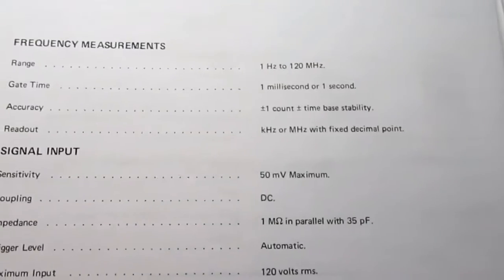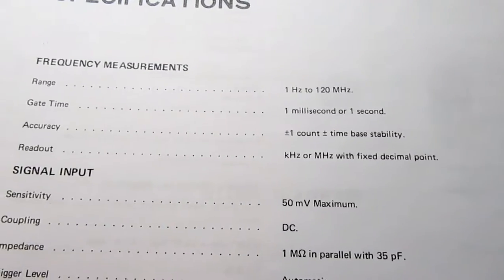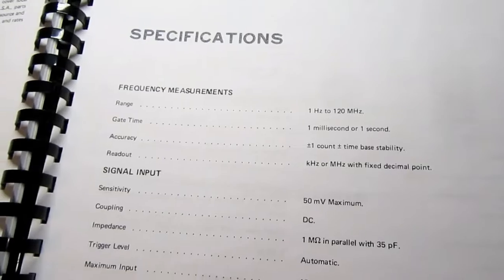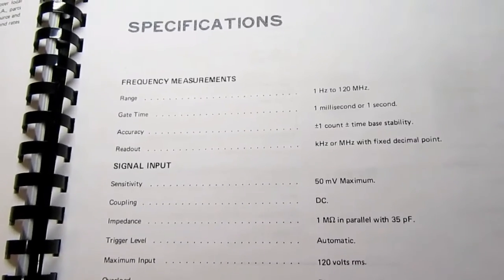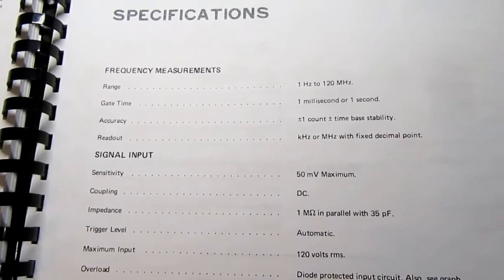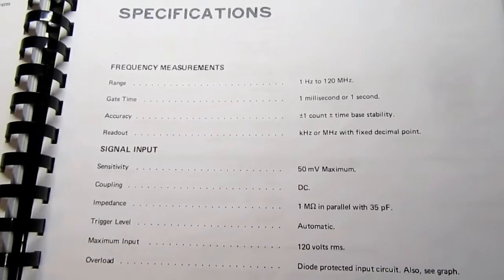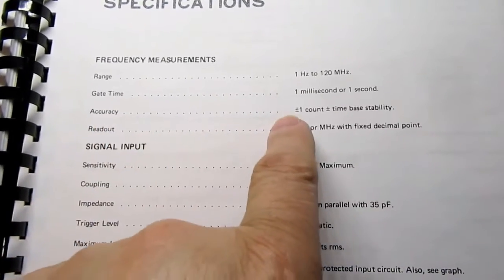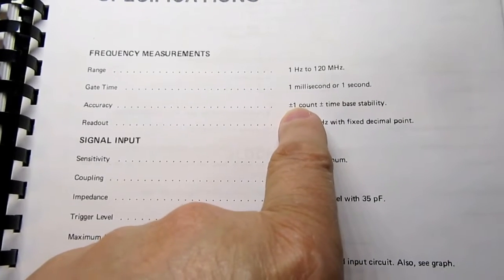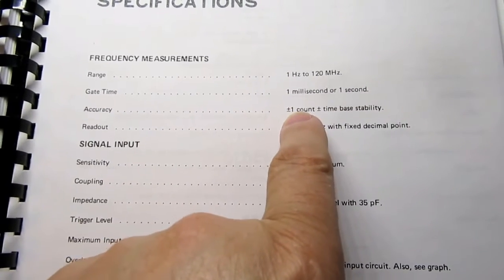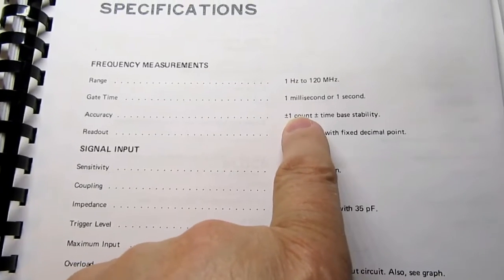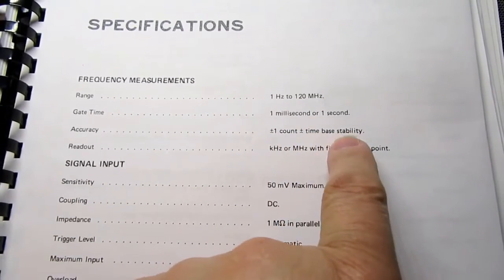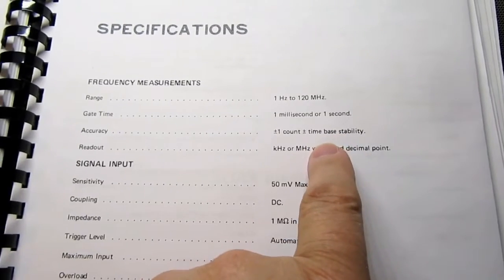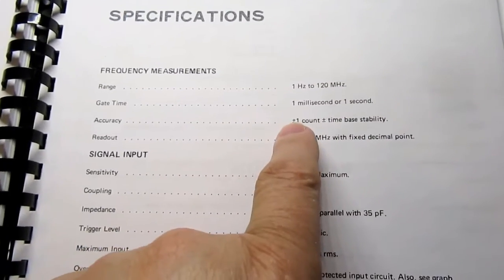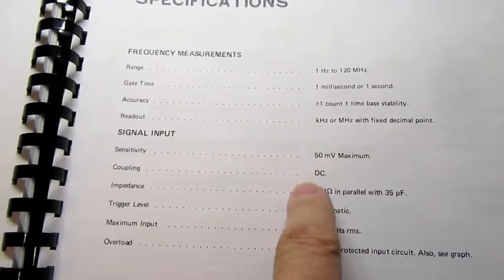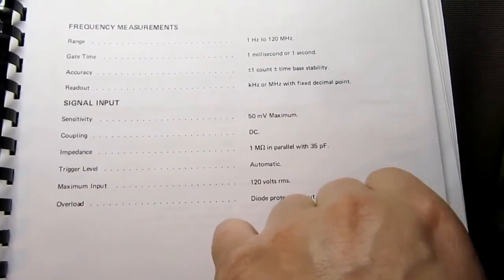Specifications. Frequency range 1 Hz to 120 megahertz. Gate time 1 millisecond, or 1,000th of a second, or 1 second. Accuracy is plus or minus 1 count, so the least significant display digit could be plus or minus 1 from the actual frequency, plus or minus the time base stability. So if your time base is off, then you've got that, plus the error of plus or minus 1 count. Readout, kilohertz or megahertz with a fixed decimal point.